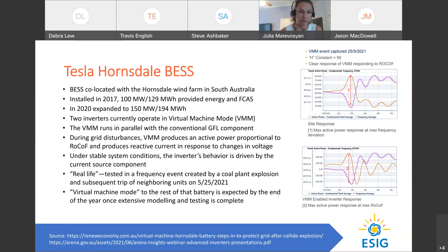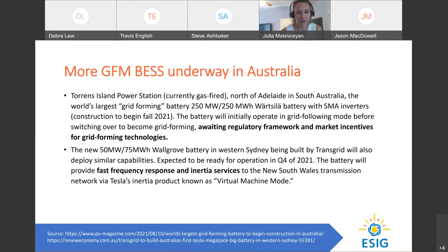There are more grid forming batteries underway in Australia. I won't read through the slide, you can go back and see it later. Basically, the message here is commercially available technology is there. They're building, but there's currently confusion or uncertainty about what the requirements will look like for provision of inertia or system strength in Australia. So some of these battery storage projects are currently building to operate in grid following mode, but are future-proofed to be converted to grid forming mode if there's some kind of incentive or clear technical specifications of what they're actually supposed to do. Next slide, please.